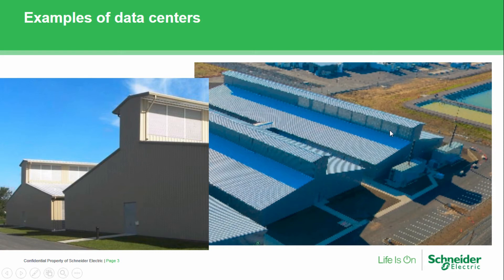Now I want to show you a different data center — this is known as the Yahoo chicken coop data center. It's unique in that it's shaped like a chicken coop. You'll notice the high-level structure at the top, called the cupola, where hot air from the exhaust of the servers comes out. Cool air comes in through the sides of the data center, goes through the servers, and after leaving the servers it's warm. That hot air naturally rises up and goes through the cupolas and out of those vents at the top — an interesting and relatively low-cost way of cooling servers, though it has to be built in the right climate.